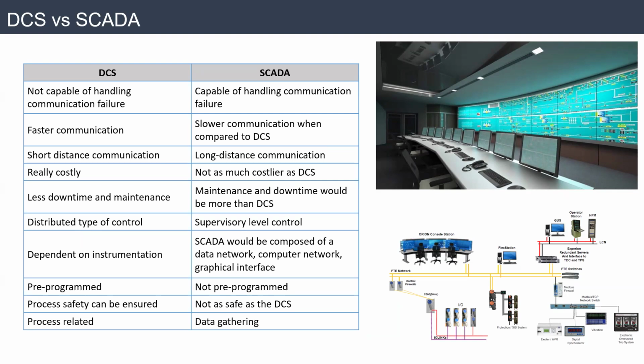On the other hand, if you are using a remote area, for example, you are monitoring and controlling oil wells. Oil wells usually will be in the desert or in the middle of the sea. So it's better to use SCADA to control and monitor these. This is remote. Most likely you will use it for data gathering. So you will collect data, do a small logic and do the control in SCADA. If a long distance is involved, SCADA is preferable. Also, it's much cheaper than DCS. If you have a small plant, it's better to use SCADA, not DCS. This is the major difference between both.